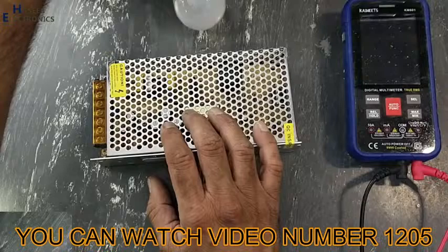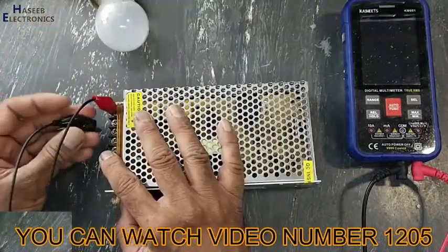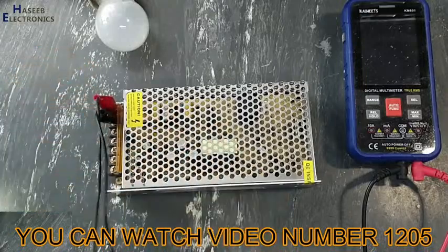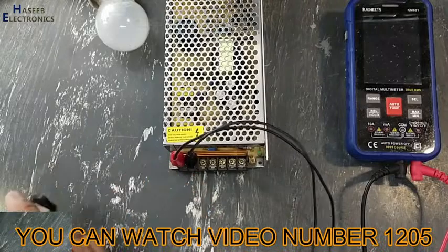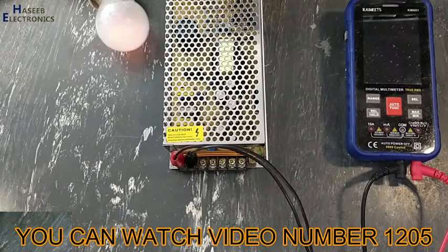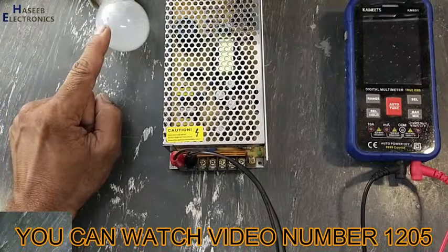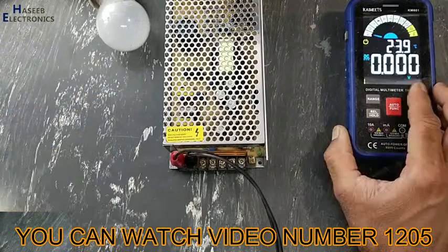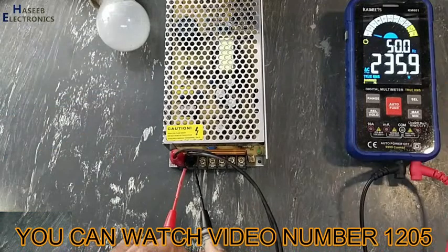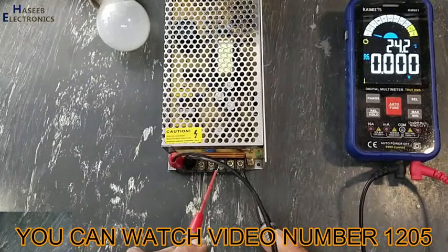I will apply power using a series lamp and we will monitor the lamp condition. I will apply line and neutral on these two terminals. The lamp draws current, that means its input circuit is clear. AC voltage 235.9 volt. Check DC output. No output.